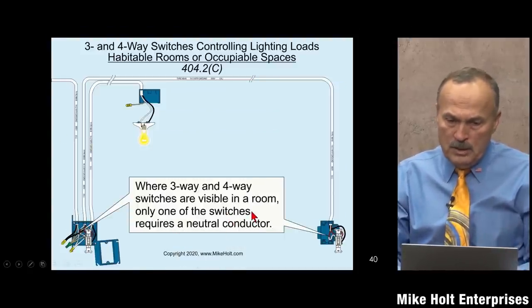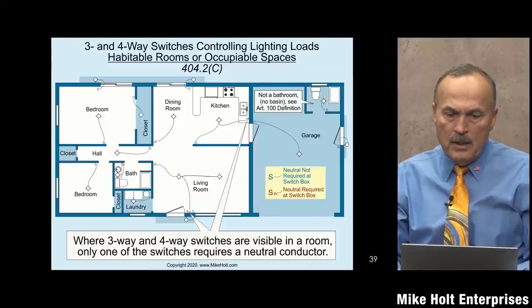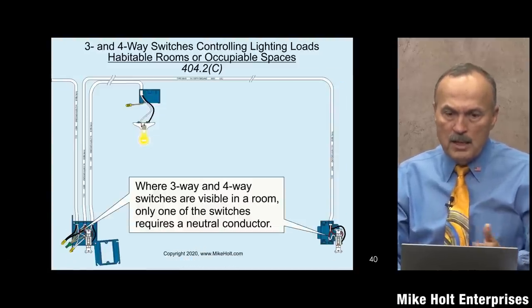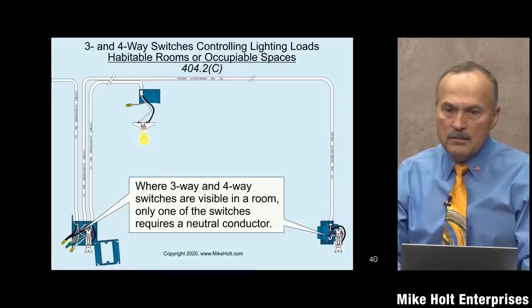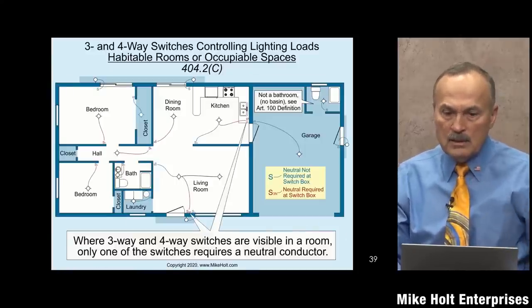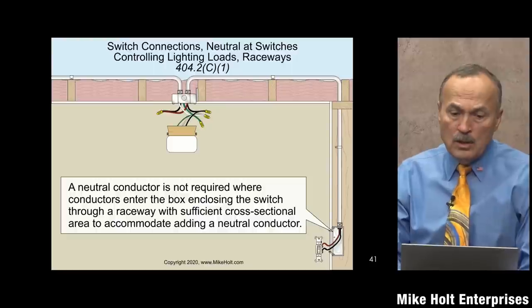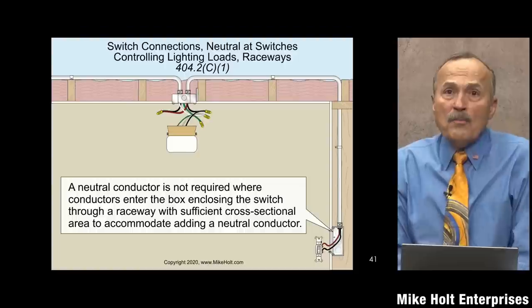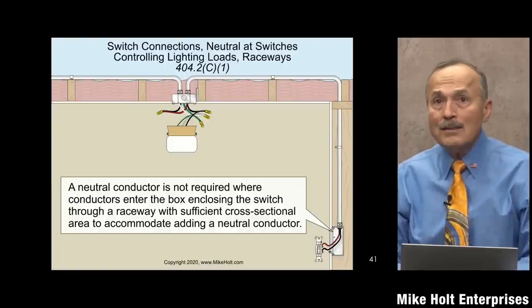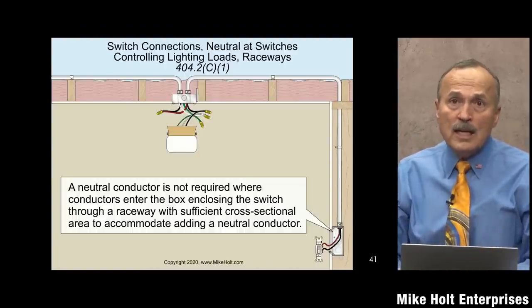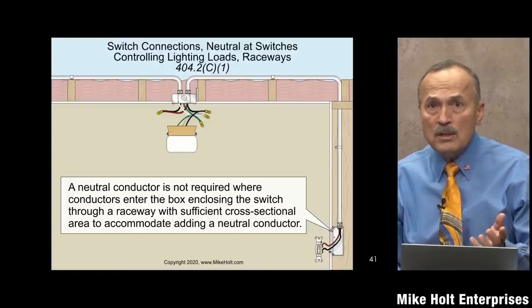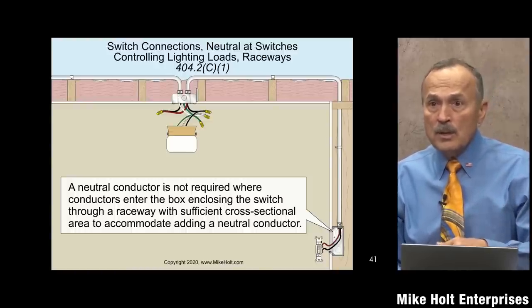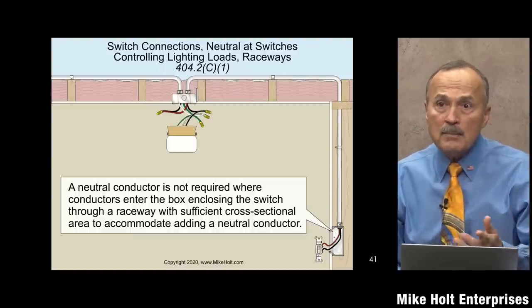Also, a neutral is not required if the wiring is installed in a raceway system. The logic is: if it's wired in conduit, you can pull in a neutral conductor later when you actually need it. So if you're in a raceway system, you don't need to pull the neutral to the switch initially — you can add it later whenever a neutral-requiring switch is installed.